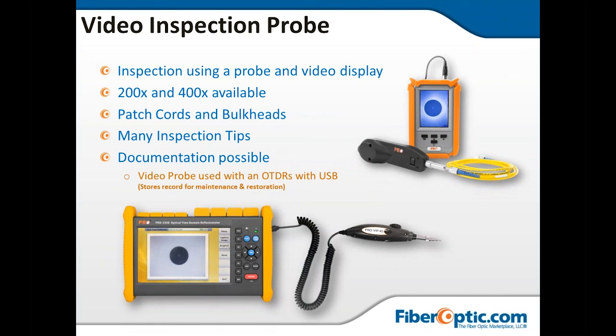Now, the video inspection probe - we'll show both of them here. The real positive is you can toggle between 200X and 400X with these units. You can also use them to inspect patch cords as well as bulkheads. When I say bulkheads, I mean anything with an adapter you have to plug into, where you can't get your inspection probe right on the tip of the fiber. A lot of times you can't go into the back end of a bulkhead and pull the connection or patch cord off, so you have to use a special tip for bulkheads to inspect that, but you'll be able to do that with the inspection probes. There's a variety of tips available for all the different connection and bulkhead types out there.